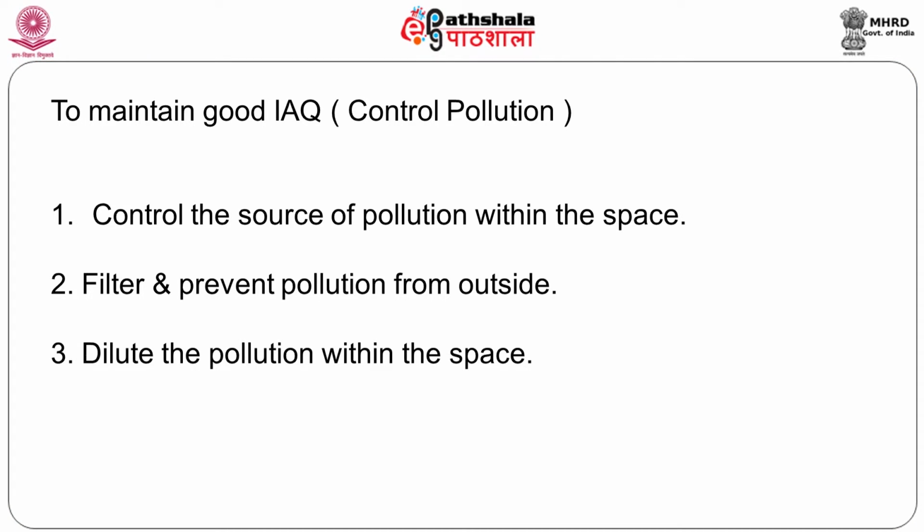Now, after both these, as I said, there are certain things which you cannot catch, you cannot minimize. So, those things you live with and effect dilution by putting in more fresh air. So, you could for instance say, look, my janitorial practice is in the morning at 9 o'clock. At 9 o'clock I have humidity added on. So, technically a good air conditioning man can say, at the time my floors are being mopped, let me increase the fresh air by 10%. Let me increase my fresh air by 20%. It will mean a marginal increase in heat load, but a phenomenal improvement in air quality.